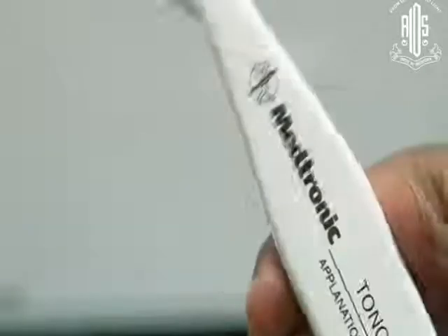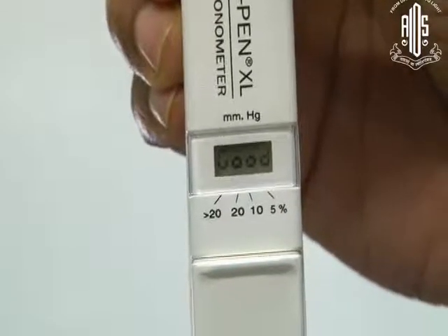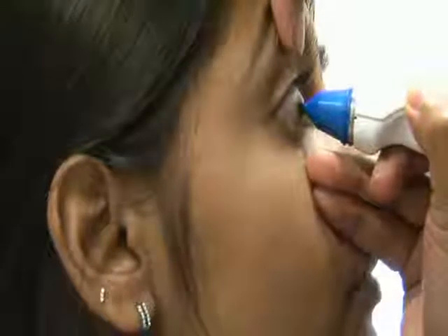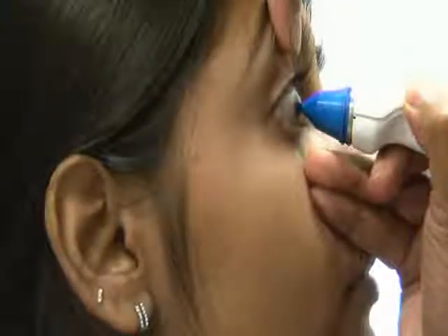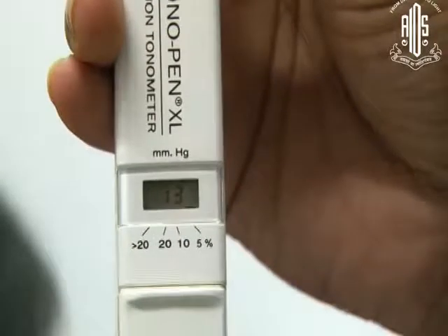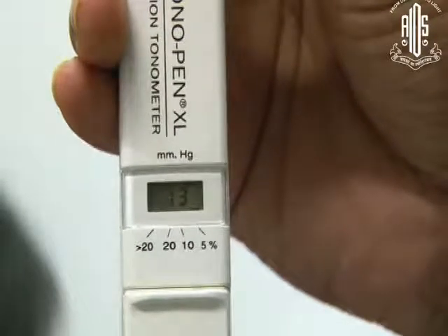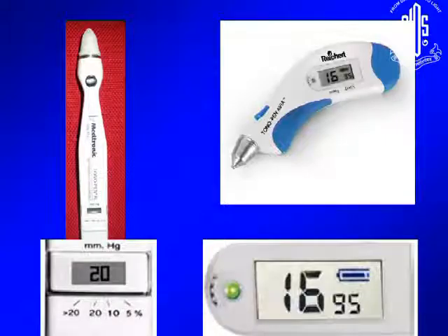What is recommended is that every day before you use the instrument, you need to calibrate it. Calibration takes about 20 seconds. If the calibration is good, you can go ahead with the procedure. And you just rest your fingers on the cheek of the patient, lift up the upper lid and applanate. So that's the pressure that you're getting there. And you also get an error reading of how reliable that pressure is. Basically, you will see a line there which tells you how reliable it is. So if the line is at the 5% mark, it tells you that the reliability is 95%, and it is recommended that you use only readings which are at the 5% mark.